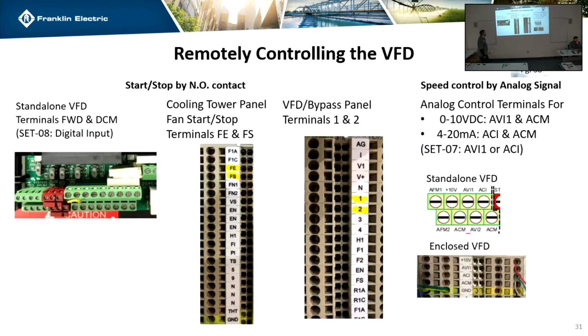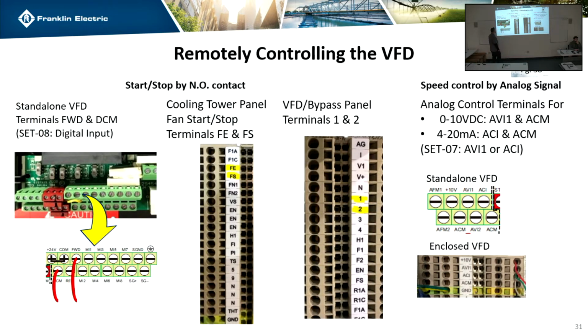So remotely controlling the VFD, this is if you get a package from us. There are two things that you're going to see. If you have a drive by itself, it's just going to be forward and DCM, and any sort of relay or jumper is going to be your run command. If you have a cooling tower, it's going to say FE and FS, which is just fan enable and fan start. And for bypasses, it's just going to be terminals 1 and 2. They're all doing the same thing. They're all closing forward and DCM. It's just that the cooling towers and the bypasses have some relay logic in between that will lock it out under certain circumstances.